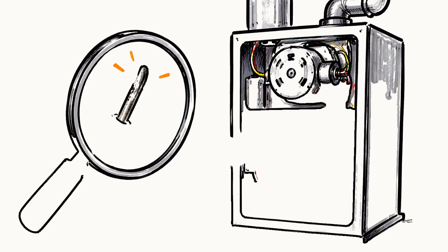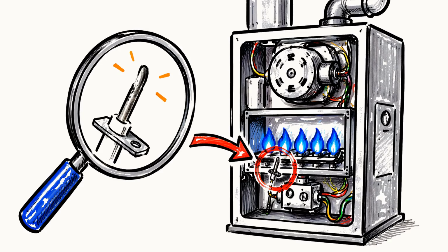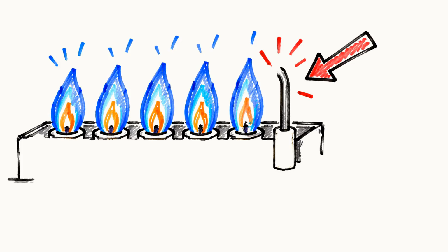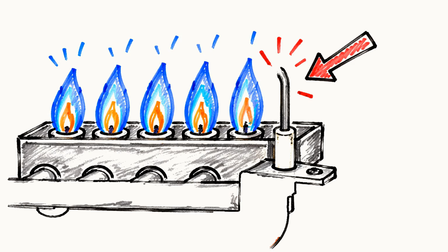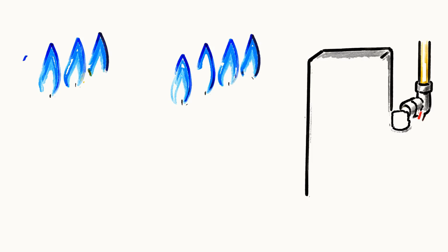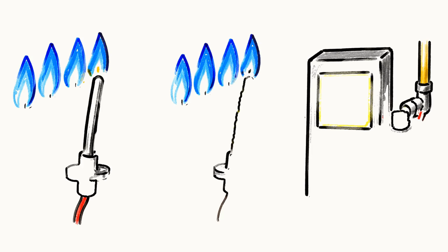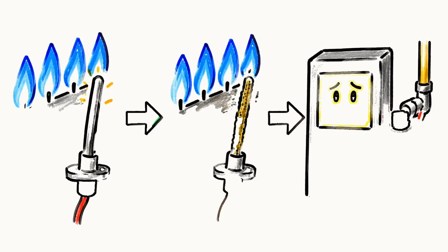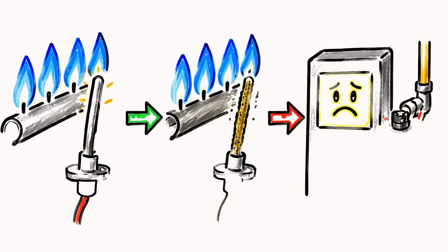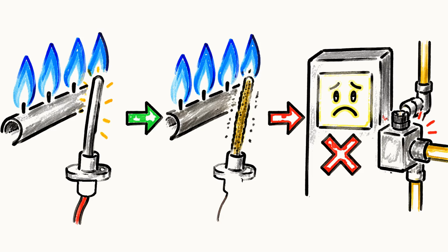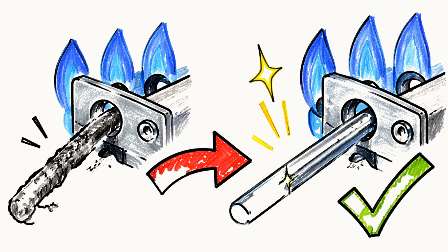The usual suspect is a dirty flame sensor. That sensor is a thin metal rod that sits in the flame and confirms to the furnace that the burner's actually lit. Over time, it gets a thin coating on it, and once that coating builds up, the furnace can no longer sense the flame. So it assumes the burners failed to light, and it shuts the gas off as a safety move, even though everything lit perfectly. The fix is genuinely satisfying.